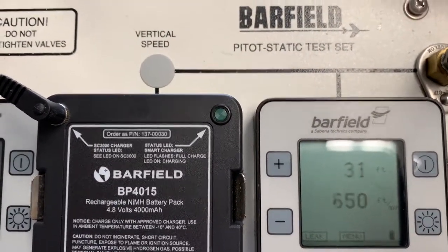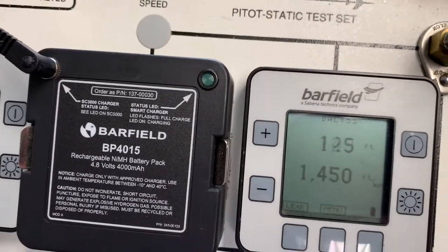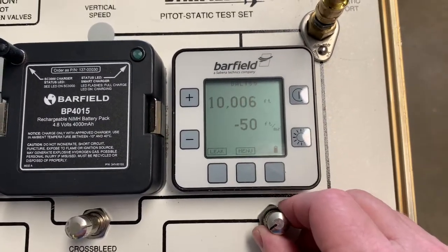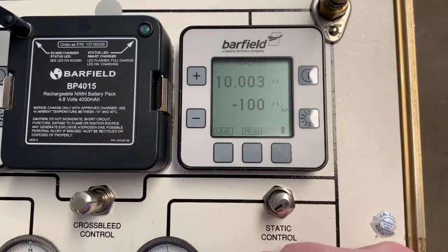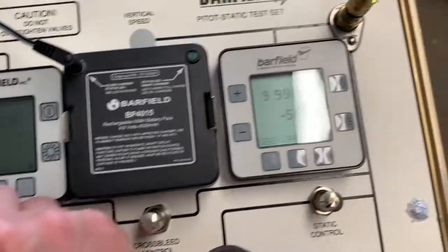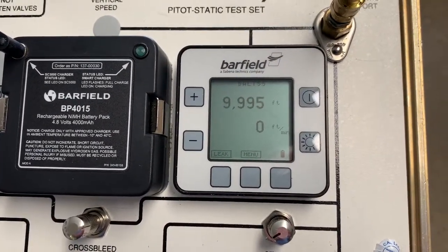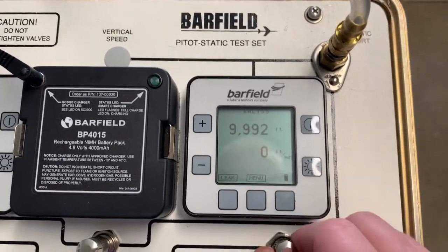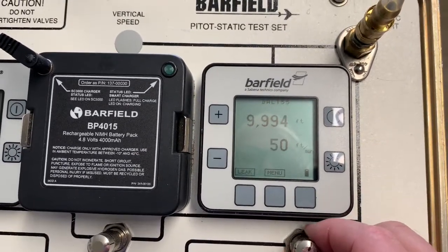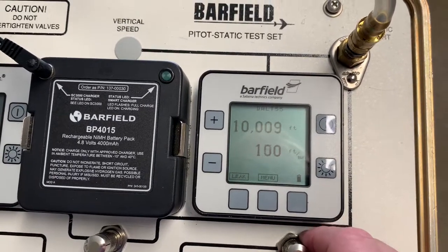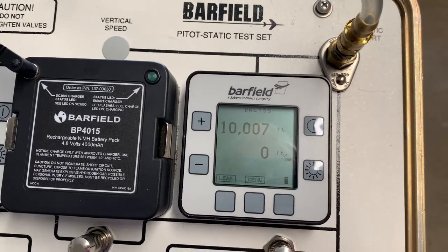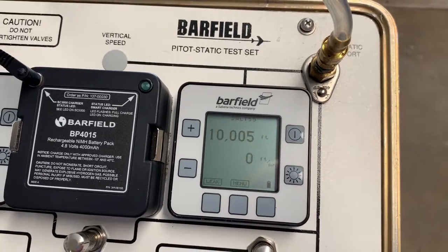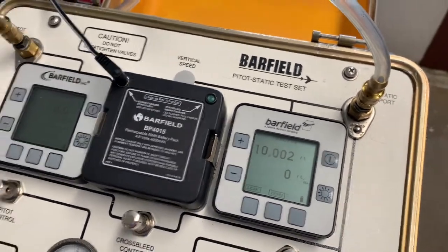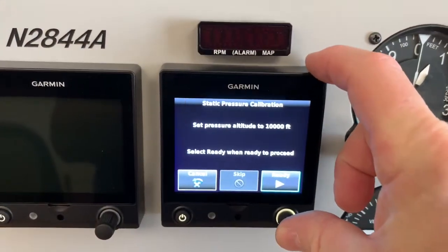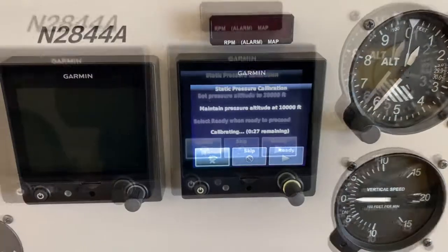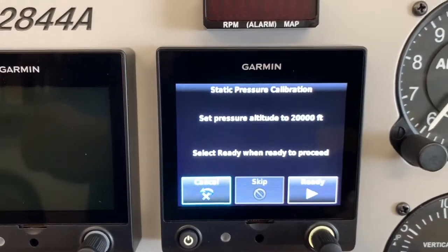So I'm going to pause the video and I'll start it up again here once we get to 10,000 feet. Okay, here we are, really close to 10,000 feet. I'm off just a little bit. Let's settle down there a little bit. Now we'll bring it back up. And you're going to have some leakage unless you got a really, really tight system. Okay, that's going to settle in right at 10,000. And we're going to go over here and press ready. You can see that we finished the 10,000. It says proceed to 20,000.